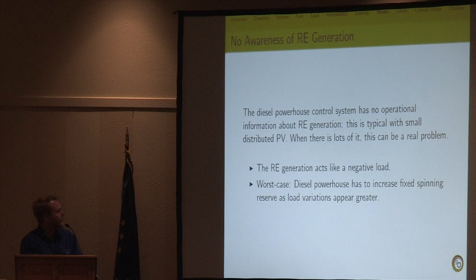Okay, so the first step, and this is what happens when you have a lot of people just putting PV behind the meter on their rooftop, is that the powerhouse doesn't necessarily know how much renewable energy is even in the system. At that point, the utility has a big problem, because if that is a significant portion of the current demand and it suddenly drops away and they don't know about it, then they potentially haven't kept enough spinning reserve, or vice versa. They have to keep much more spinning reserve just because there is renewable energy on the system they don't know about, but that could suddenly break away and just look like a massive motor start, and they have to match that with their diesels. So that can be a big issue.